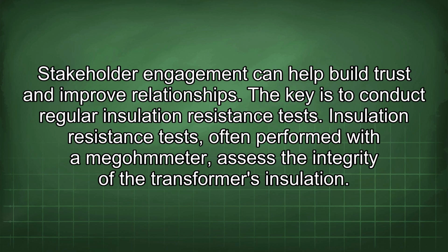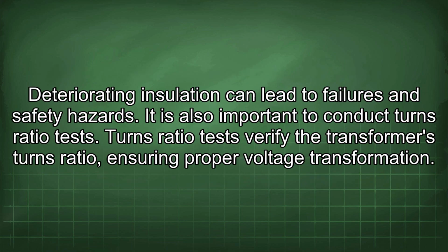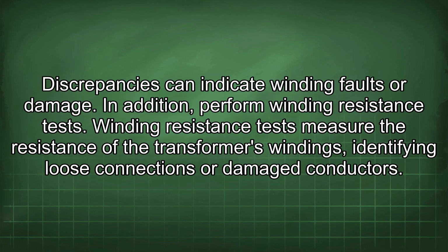The key is to conduct regular insulation resistance tests. Insulation resistance tests, often performed with a megohmmeter, assess the integrity of the transformer's insulation. Deteriorating insulation can lead to failures and safety hazards. It is also important to conduct turns ratio tests. Turns ratio tests verify the transformer's turns ratio, ensuring proper voltage transformation. Discrepancies can indicate winding faults or damage.